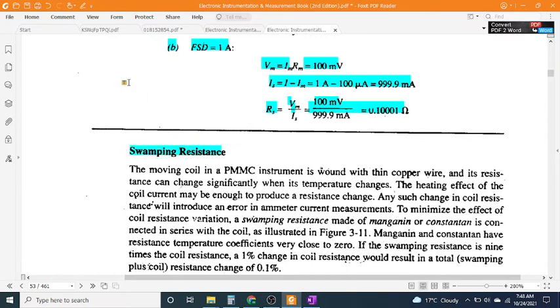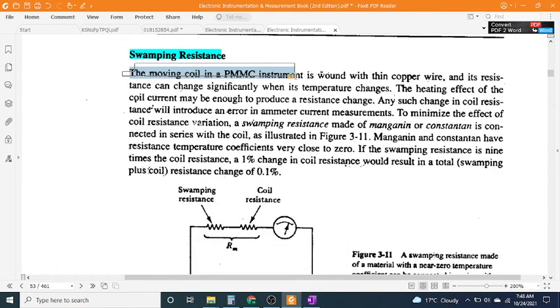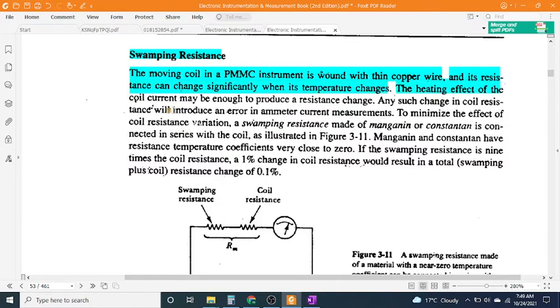Swamping resistance: The moving coil in a PMMC instrument is wound with thin copper wire, and its resistance can change significantly when its temperature changes. The heating effect of the coil current may be enough to produce a resistance change. Any such change in coil resistance will introduce an error in ammeter current measurements.